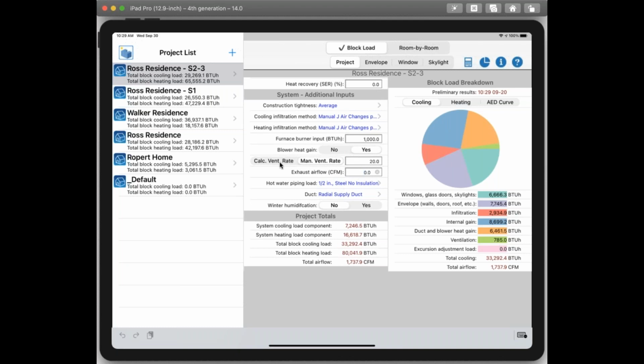So it's either or. Ventilation is calculated based upon the ACCA Manual J8 formulas, and there are a number of factors that go into calculating ventilation. Not only the volume of your home, but also the infiltration. Because if you think about it, if you have infiltration coming in, but you also have ventilation, there's going to be some positive, negative pressure issues going on, and also exhaust too. So all these values are taken into account when calculating your ventilation rate.